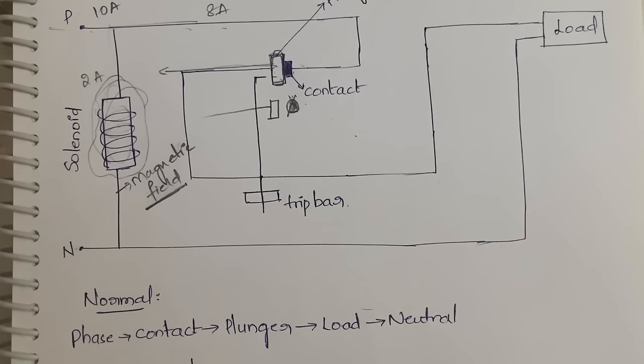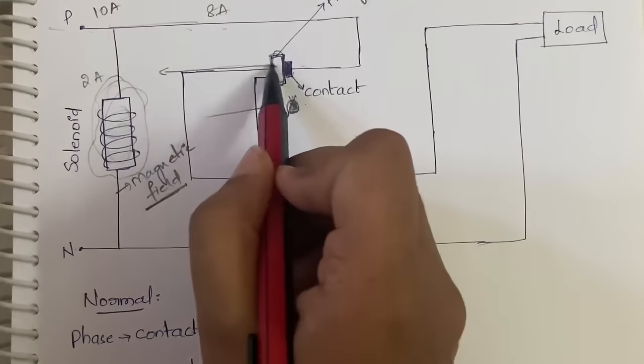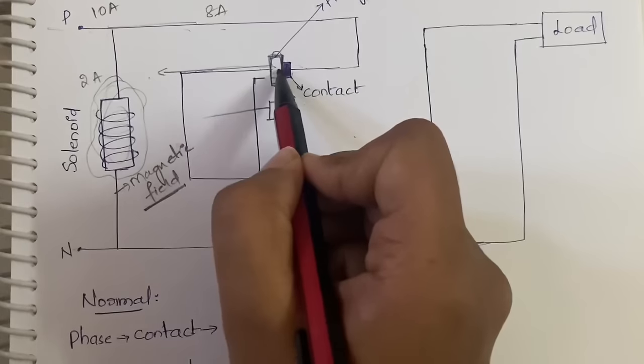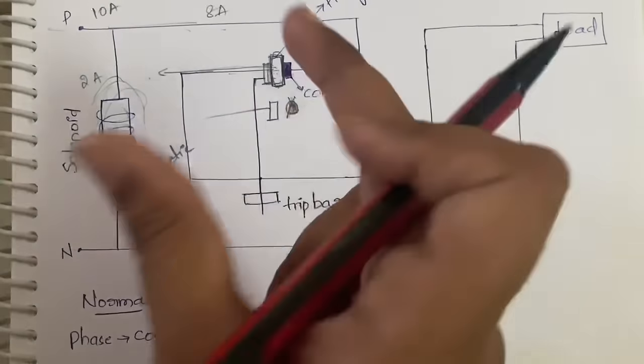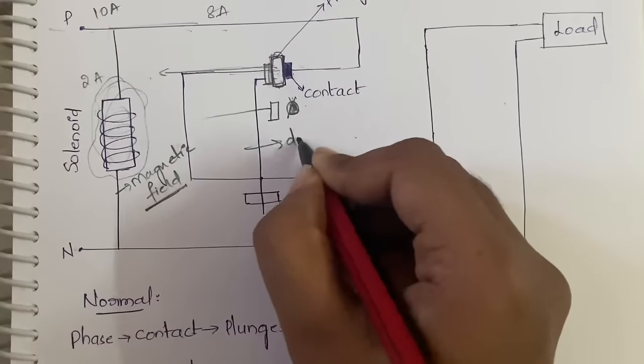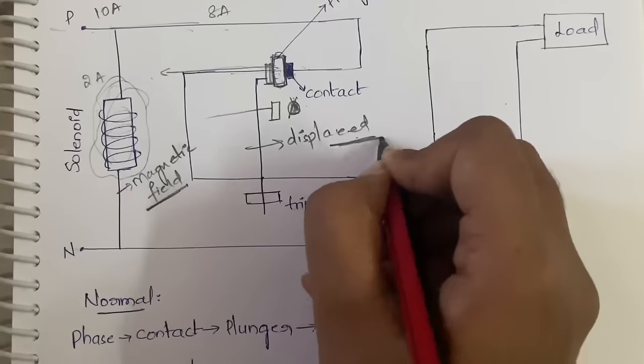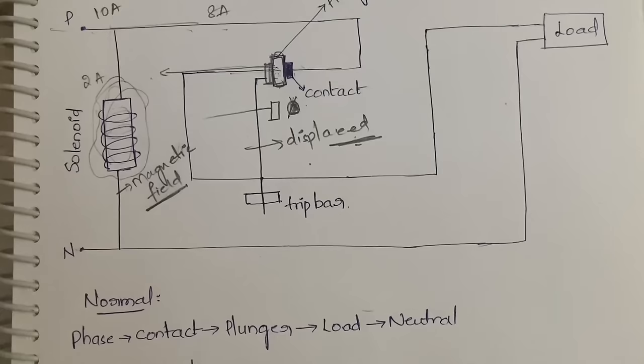Now, how does the MCB switch turn off? Both things must happen simultaneously: the circuit must become open and the switch must turn off. As the plunger moves backward toward the solenoid it hits the trip bar. The trip bar is displaced from its position, strikes the MCB switch, and the switch turns off. Again, you need to manually turn it back on to restore normal operation.